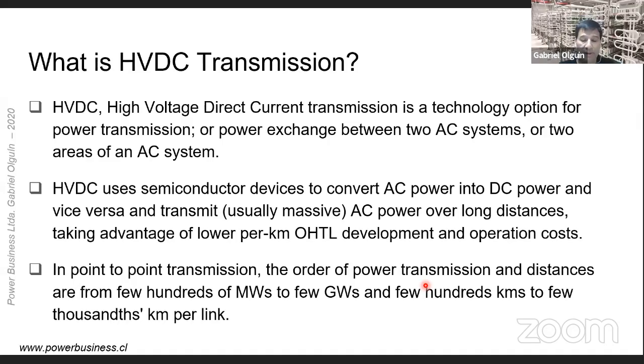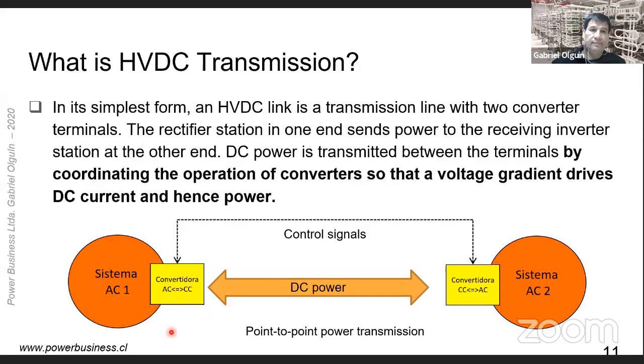In a point-to-point transmission, the order of power transmission and distance are from a few hundred megawatts to a few gigawatts, and a few hundred kilometers to a few thousand kilometers per link. In its simplest form, an HVDC link is a transmission line with two converter terminals. The rectifier station at one end sends power to the inverter station at the receiving end. DC power is transmitted between the terminals by coordinating the operation of the converters so that a voltage gradient drives DC current and hence power between the terminals.